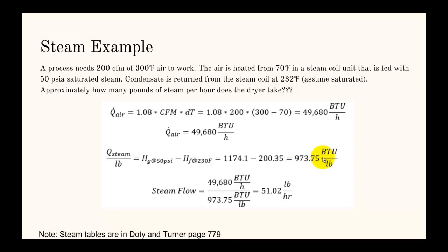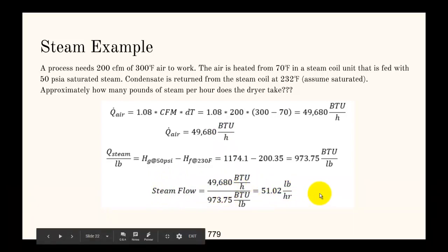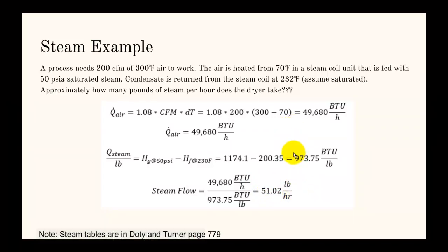You know you can deliver this many BTUs per pound, and you need this many BTUs per hour. So you look for the steam flow in pounds per hour, and you basically divide those two numbers. You get about 50 pounds an hour. The idea is you need to figure out how much heat you need, how much heat you can deliver per pound with steam, and then you figure out the steam flow there.